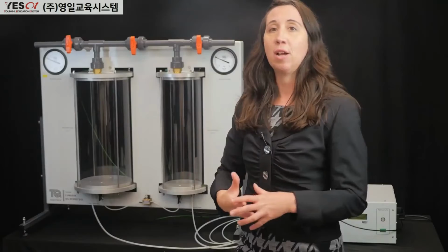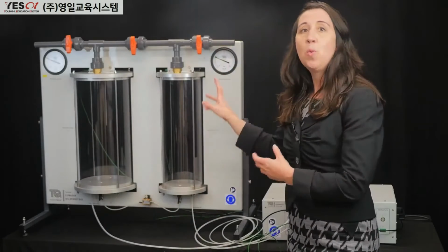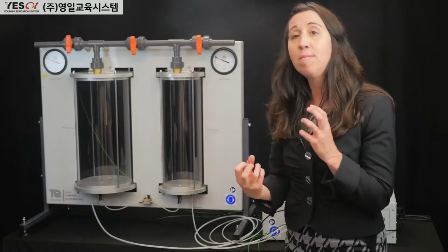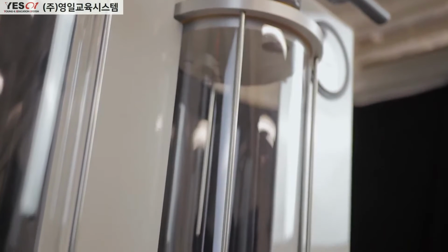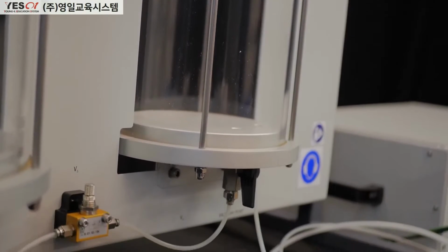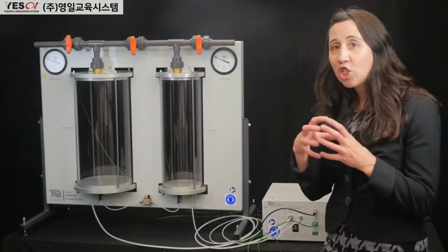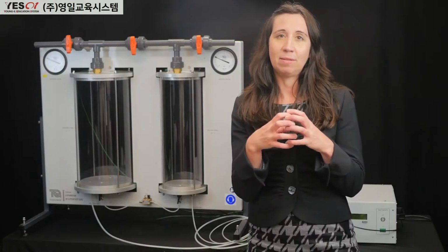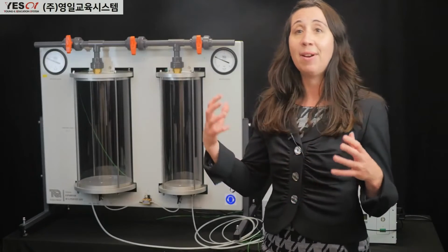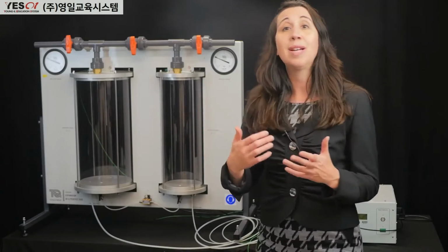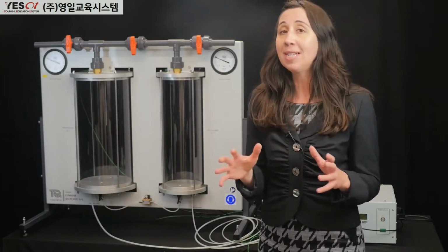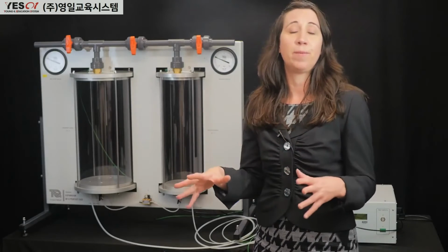Now some more detail on the vacuum vessel, which can be used as either a vacuum or atmospheric tank. The top flange has both vacuum pressure and temperature sensors. Then the bottom flange features a vacuum port that can be connected to the vacuum port on the control box to allow you to extract the gas from the vessel. One thing you don't want is air entering it when it shouldn't, which is why it is self-sealing and will automatically seal when the pipe is removed.